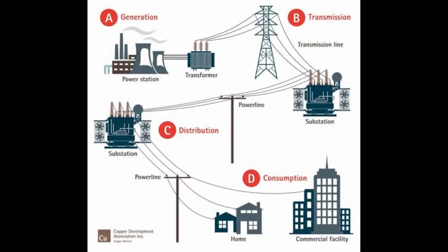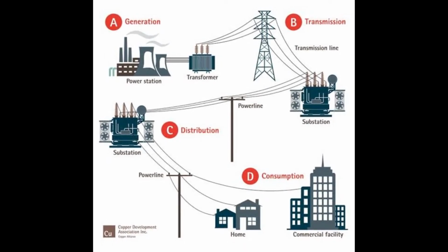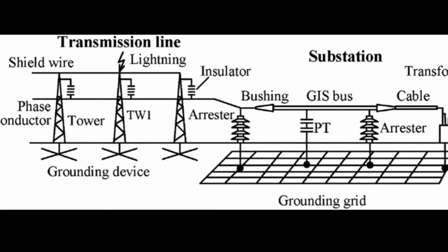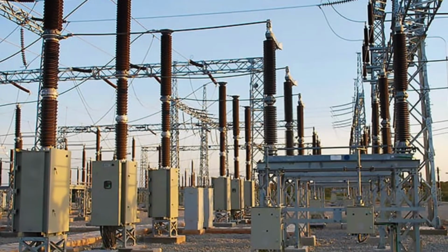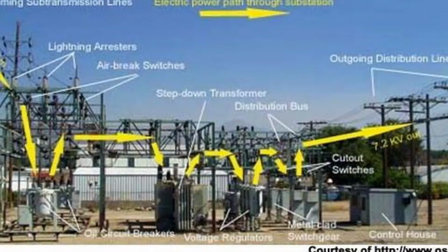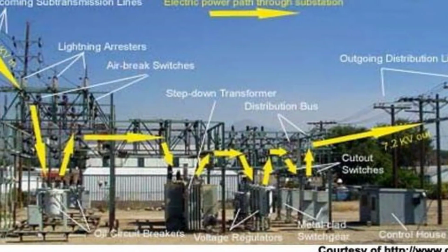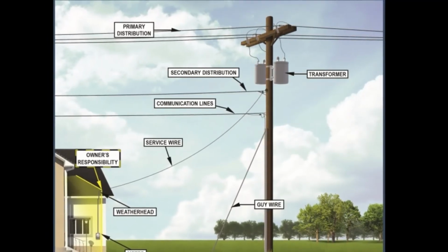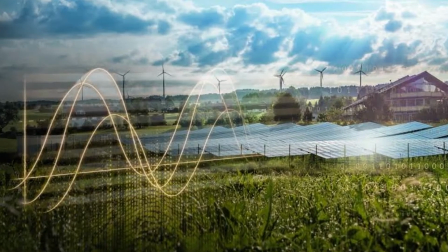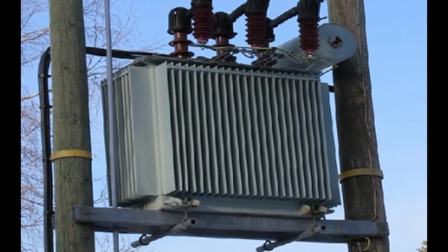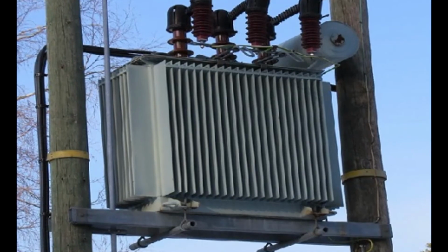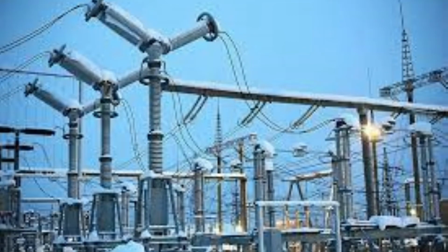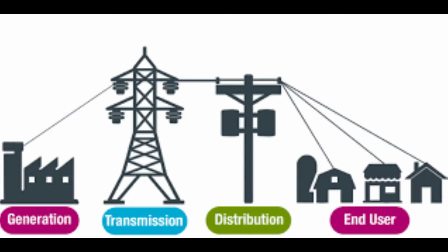Distribution is the final stage in the delivery of power. It carries electricity from the transmission system to individual consumers. Substations connect to the transmission system and lower the transmission voltage to medium voltage ranging between 2 kV and 35 kV. Primary distribution lines carry this medium voltage power to distribution transformers located near the customer's premises. Distribution transformers again lower the voltage to the utilization voltage. Customers demanding a much larger amount of power may be connected directly to the primary distribution level or the subtransmission level.